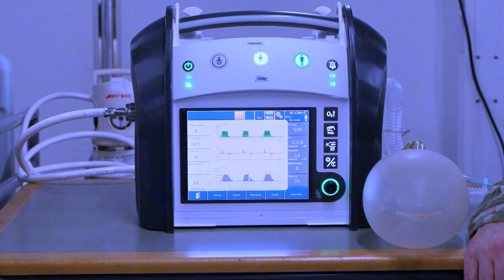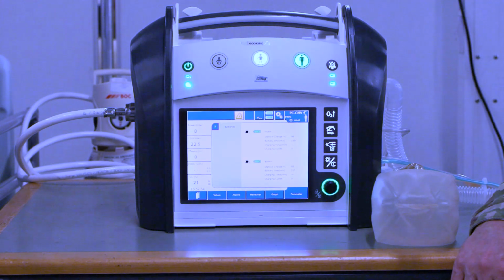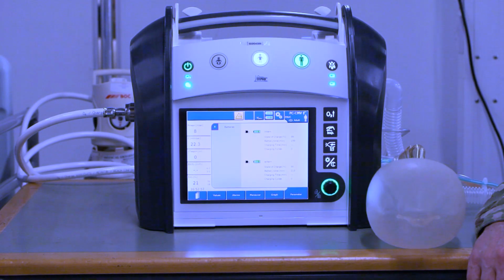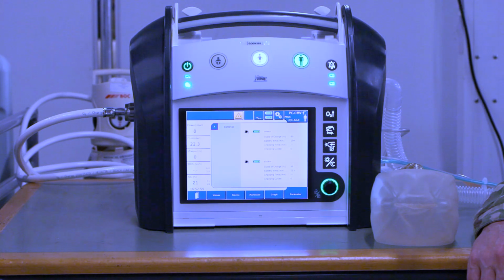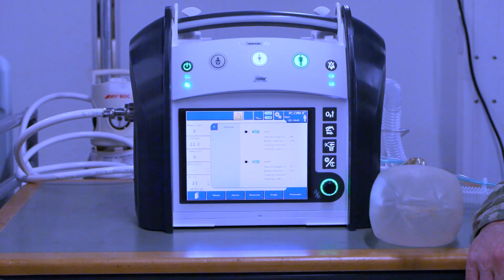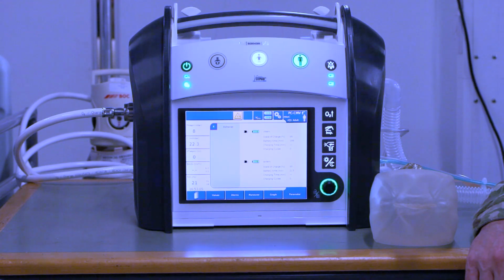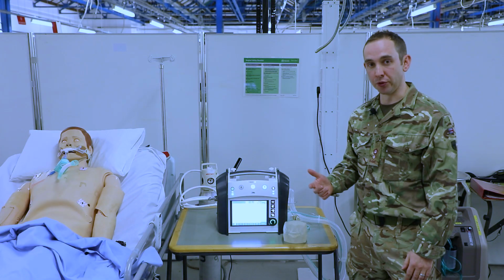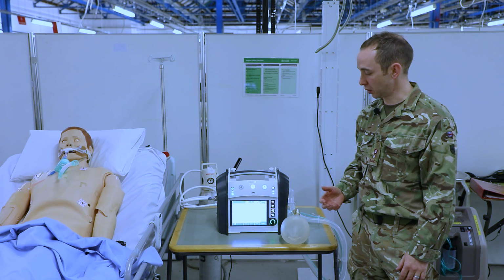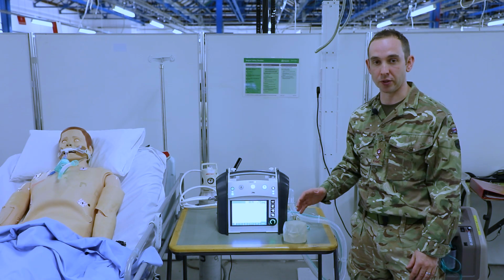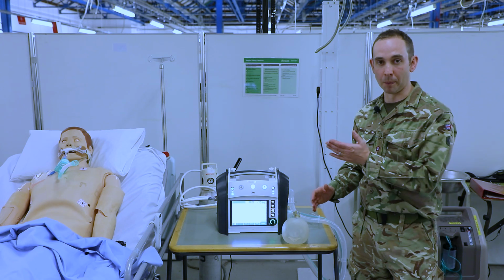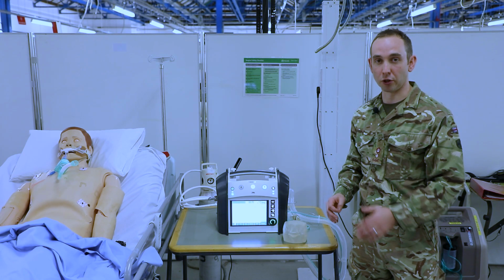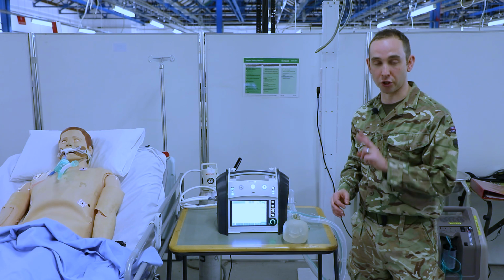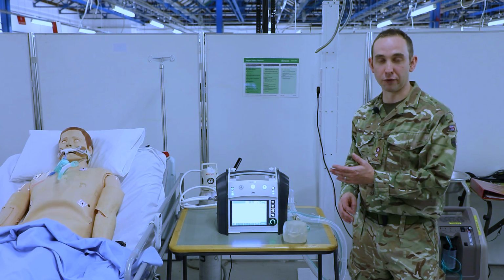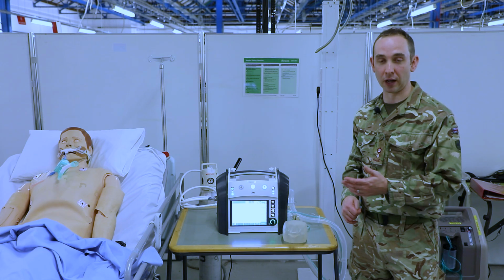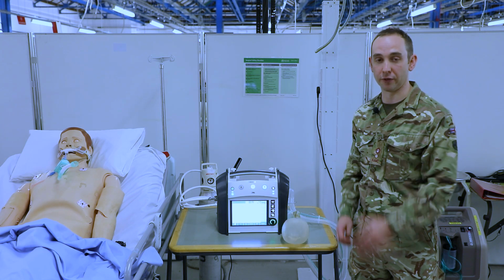Clicking on the battery button will give you information about the state of charge of the batteries, how much time is left in the charge, the charging time if it's still less than 100% charged, and also the charging cycles themselves. So every 6 months you need to do battery maintenance. This involves completely discharging the batteries, both batteries, by running the ventilator, recharging them back up, and then discharging the batteries again. So a complete discharge and recharge on 2 occasions, and then charging the battery back to full power afterwards, and that will ensure that the batteries have a good battery life.